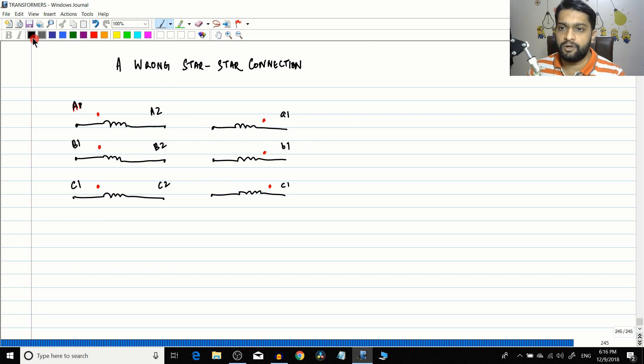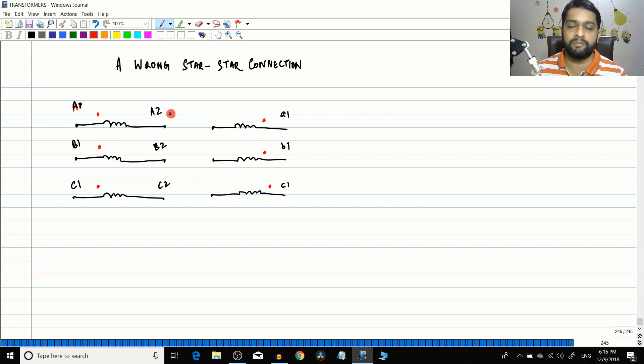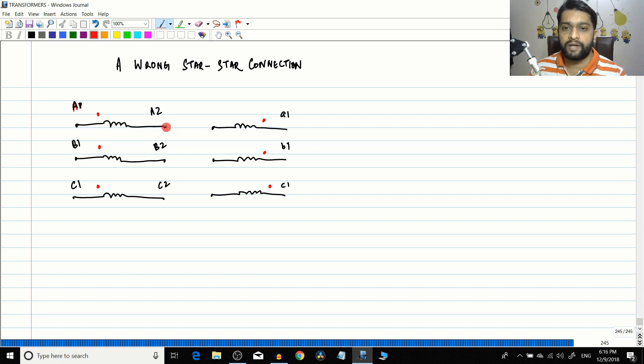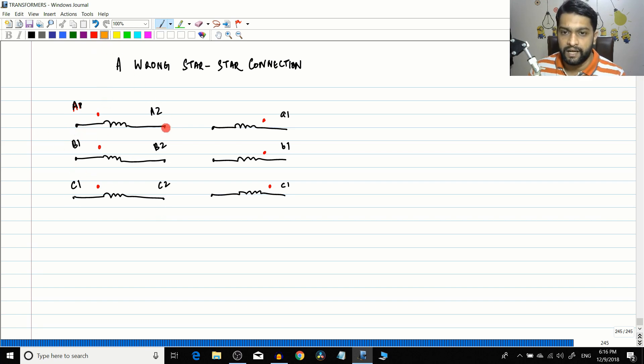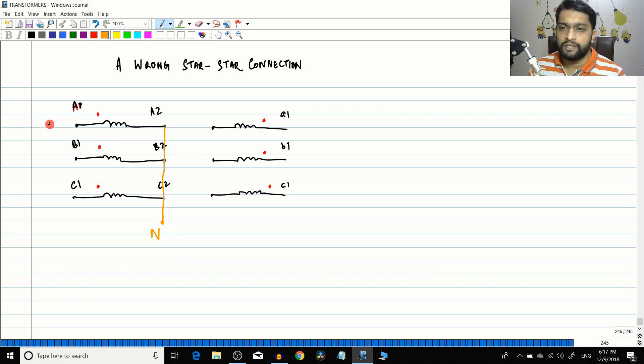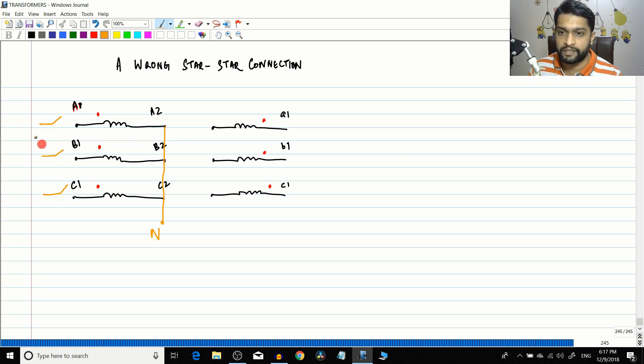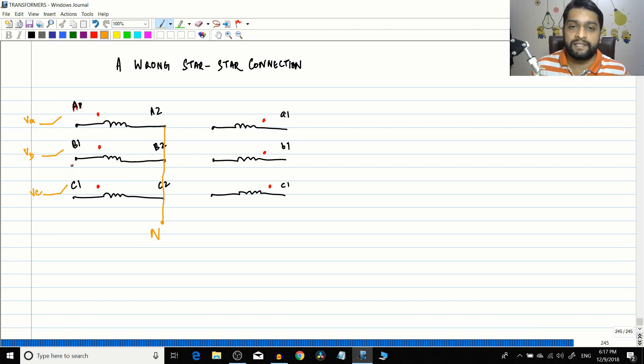In a star connection, you connect similar ends together. You can connect either A1, B1, C1 together and supply voltages to A2, B2, C2, or connect A2, B2, C2 together and supply voltages to A1, B1, C1. The neutral point N is formed at the primary side. You can apply a three-phase balanced voltage Va, Vb, Vc here. Balanced three-phase voltages have the same RMS value but differ in electrical angle.